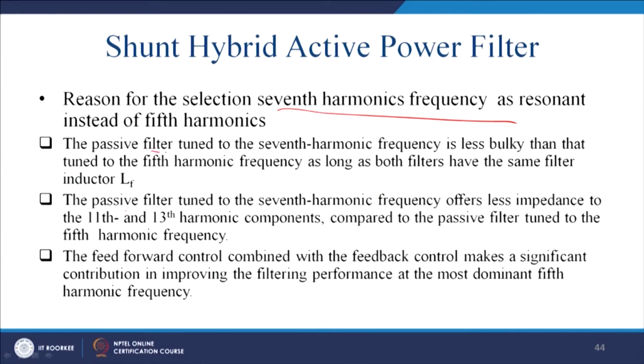So, the passive filter tuned to the 7th harmonic frequency, as I was telling, is less bulky than that tuned to the 5th harmonic, as long as both filters have the same inductance LF. Because if you keep the value of LF constant and change the value of CF, then of course the capacitor will be bulkier. The passive filter tuned to the 7th harmonic frequency offers less impedance to the 11th and 13th harmonic components compared to the passive filter tuned to the 5th harmonic frequency. So, this is also one of the reasons, and we are going for overall cost optimization and performance optimization, that this topology fits rightly into the system.